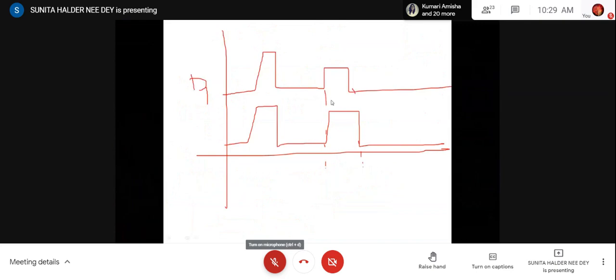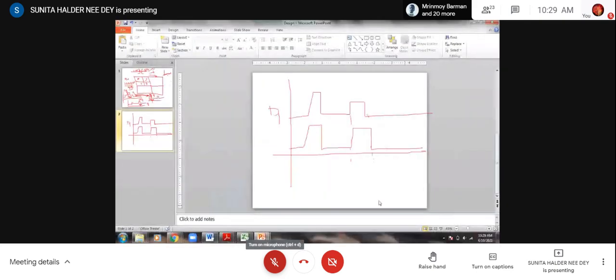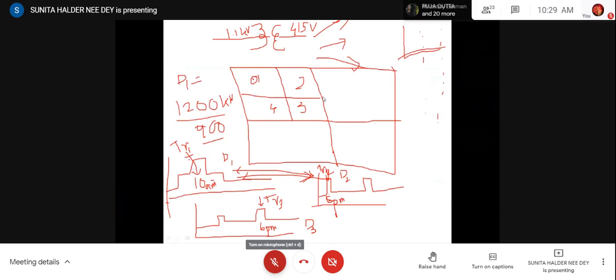Say in between these two sub-blocks, some data is not the same. Say here the maximum demand is occurring at 4 p.m., only for example, and here it is at 6 p.m. Then from the table you can notice which load is changing. Or you just decrease the area of this one and shift this area to this sub-block, so that the load can be balanced and the maximum demand can be made the same.